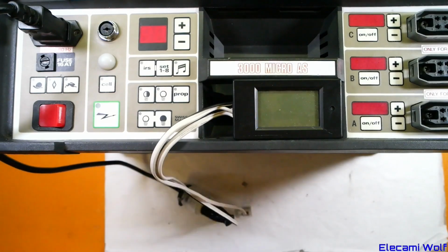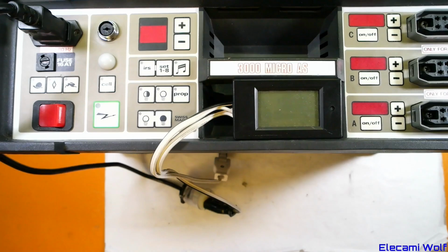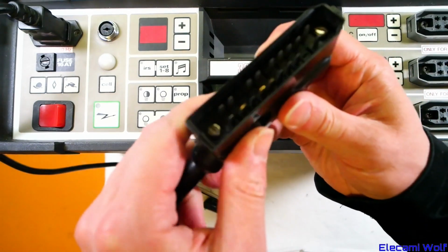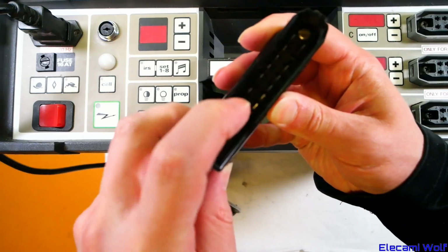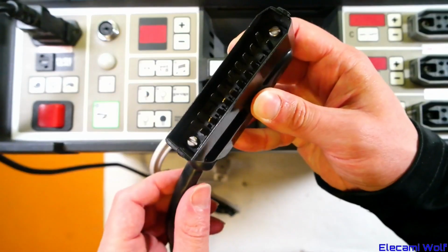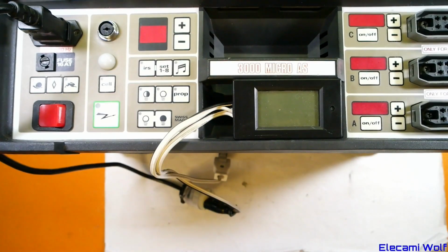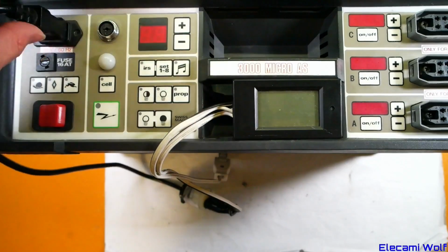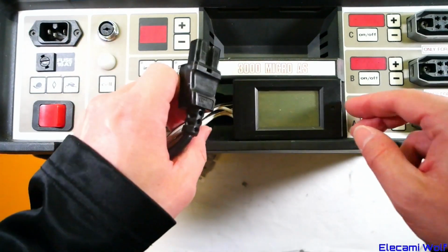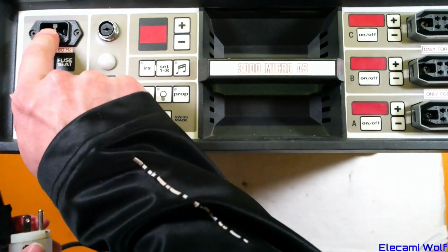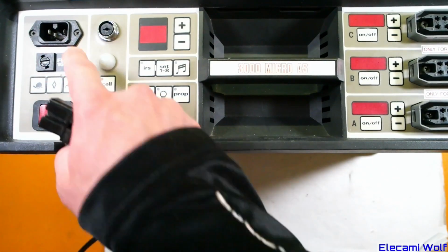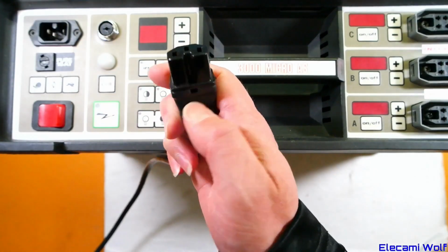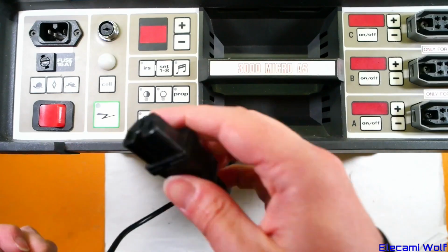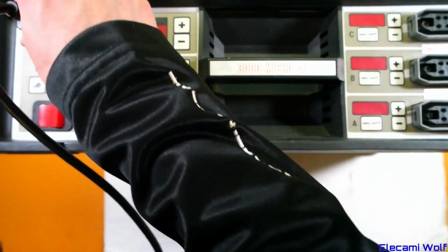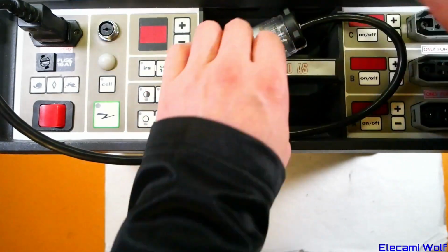So it can be incredibly dangerous when connecting and disconnecting these. If you're not being careful, you can actually see on that other one that we didn't use, I've already had a go with whoever previously owned it. It's arced away those. Maybe it got pulled out while it was firing, or maybe it accidentally misfired while the connector was being pulled in or taken out, just by the order of what pins connect and disconnect in. Annoyingly, it's got that high temperature type connector, IEC connector, so I had to find one that would fit in there and wire a plug onto it, because I couldn't find any molded-on cables with that type of connector. It's not very common. I'm glad it still works. I hadn't used it for ages.